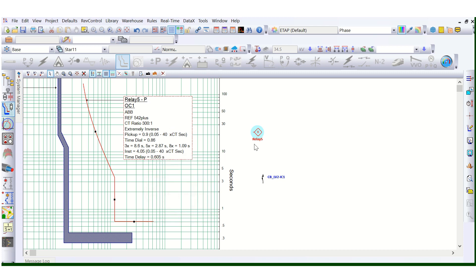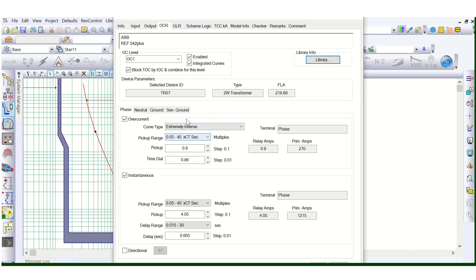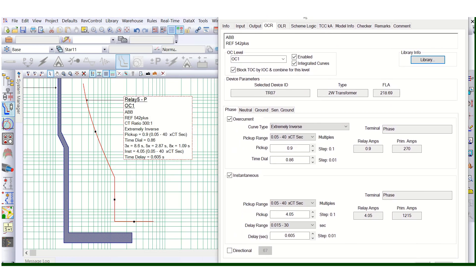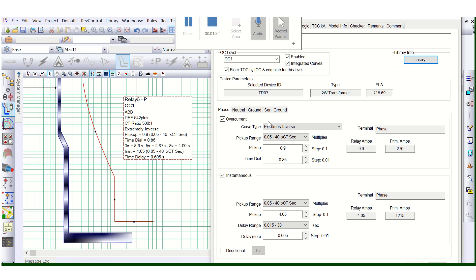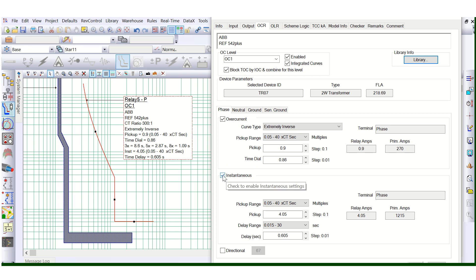Let's go to the relay setting page — overcurrent delay. We will try to understand by changing the values in the individual settings what the impact is on this curve. First of all, let's uncheck this 50, the instantaneous setting.